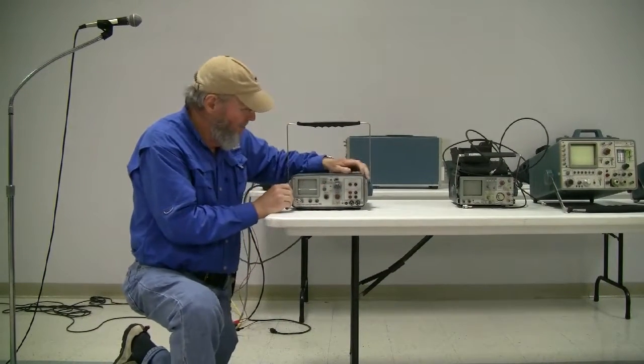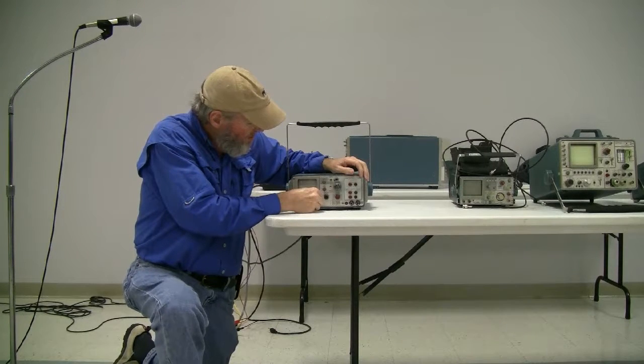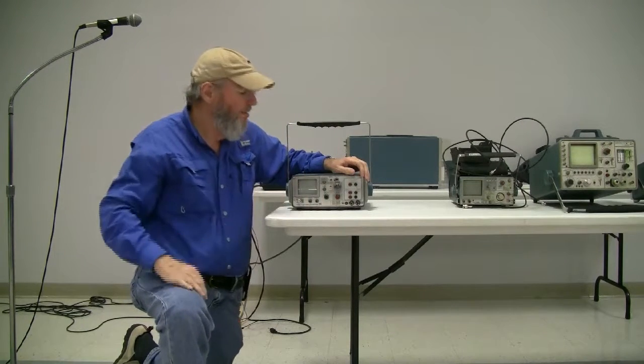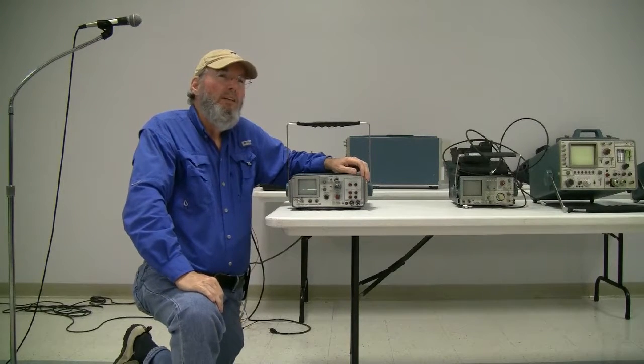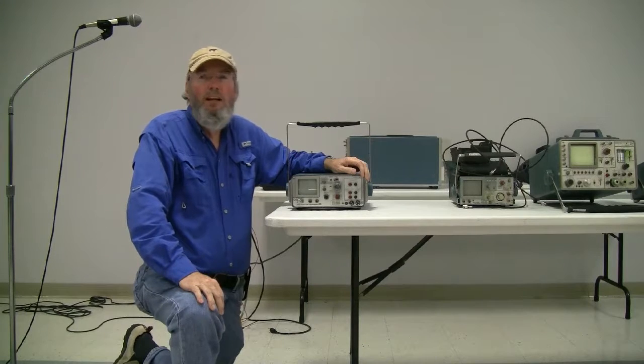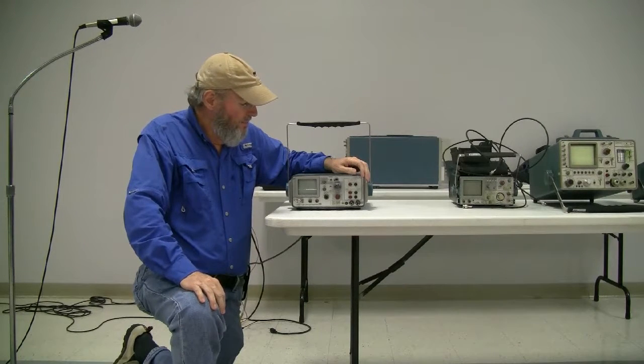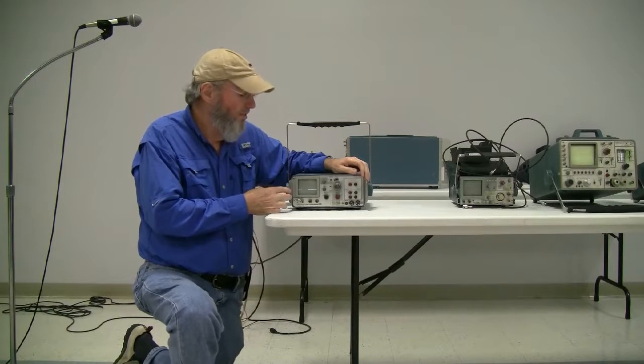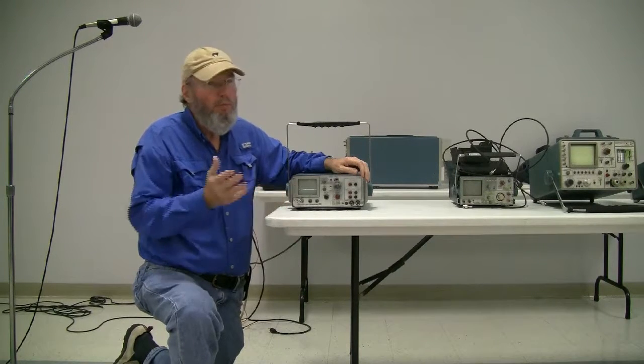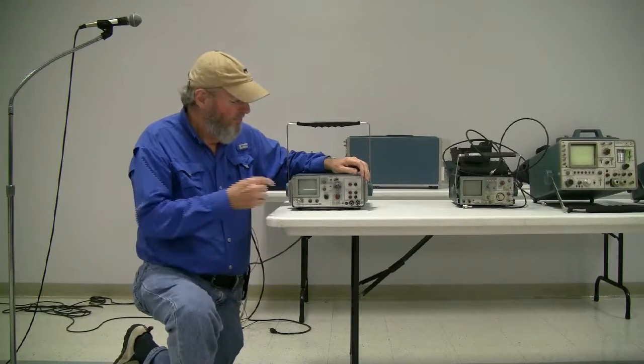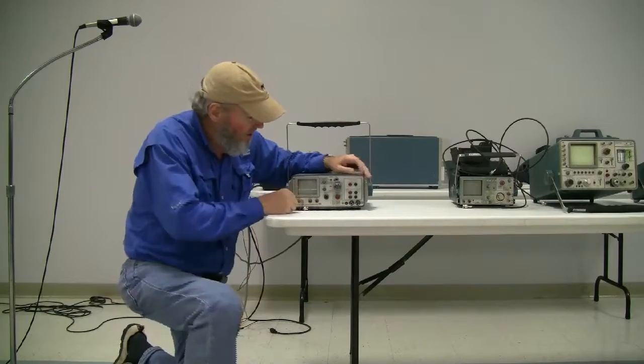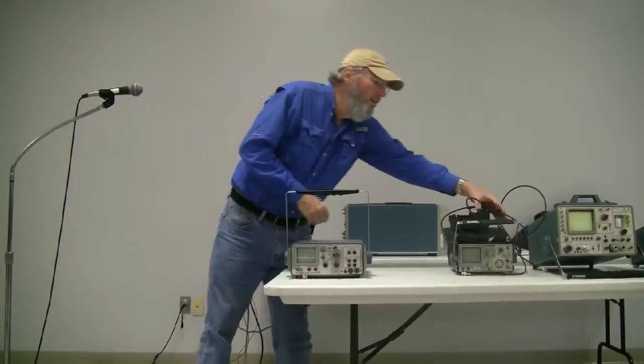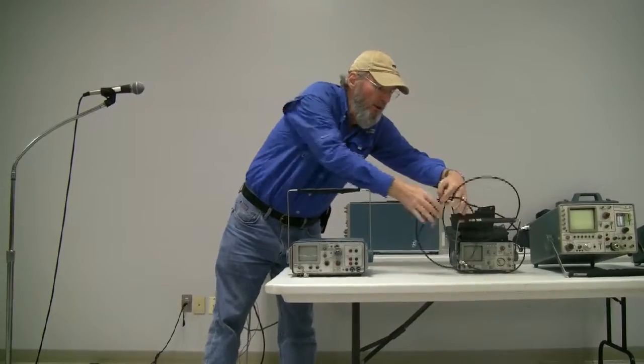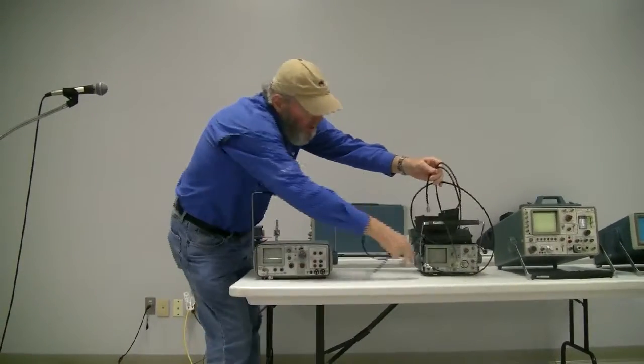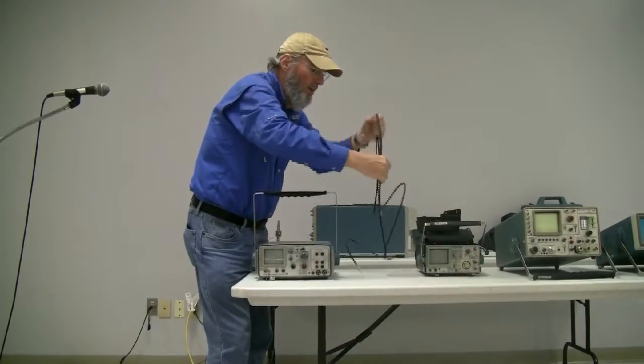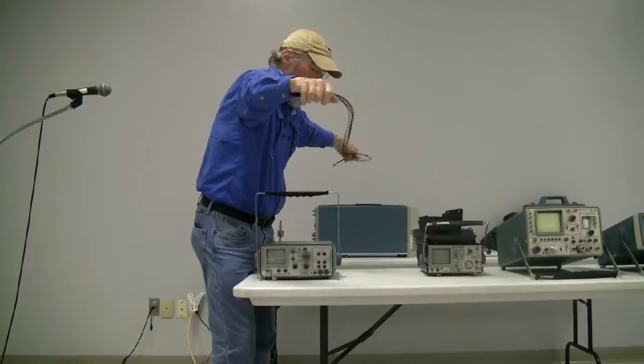This is a small display, and I'm sorry about that, but this unit is an extremely fast oscilloscope, probably with a bandwidth of 10,000 megahertz, something like that. But it also has an extremely fast rise pulse generator in it, probably 25 picosecond rise time. What this unit will do, it sends that pulse down cable and watches what comes back. And from that, you actually see what's going on at all points down the cable, including at the other end.